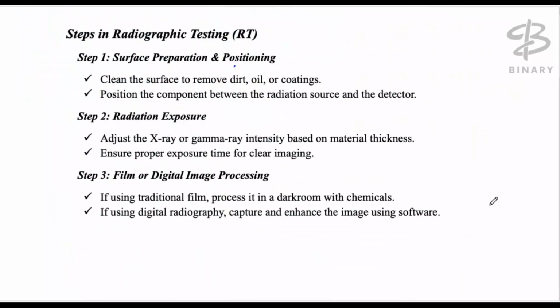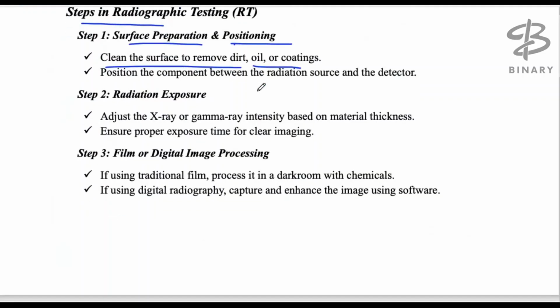Now, the part which is very important is the steps in radiography testing. The first one is surface preparation and positioning. Clean the surface to remove dirt, oil, or coating, which is very obvious. Position the component between the radiation source and the detector.